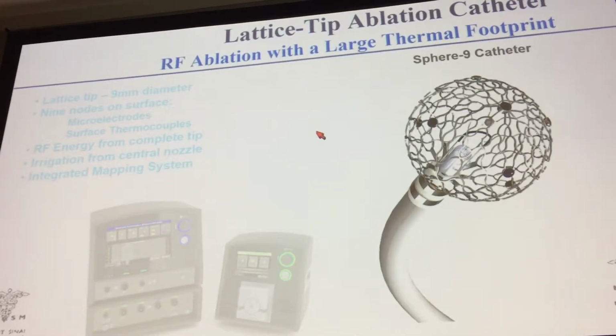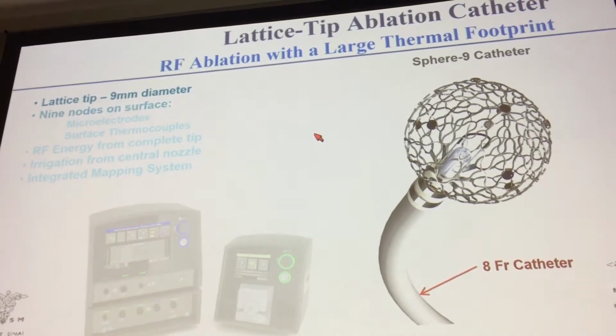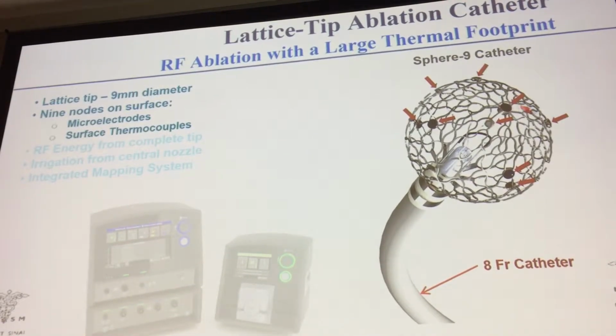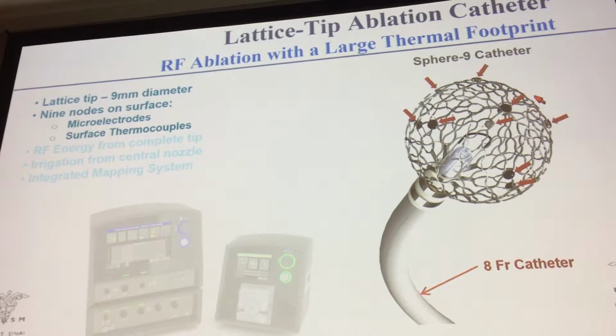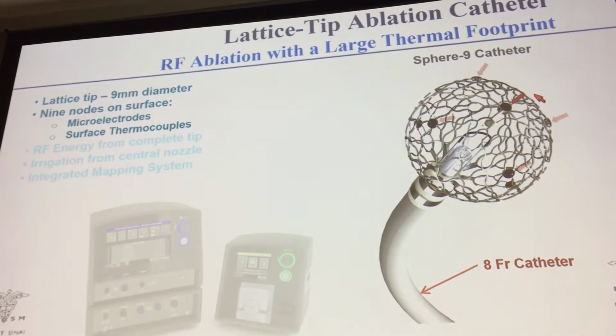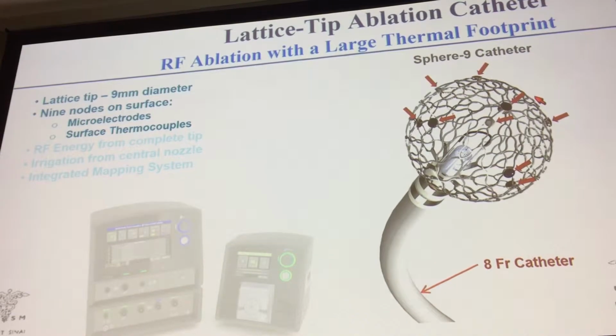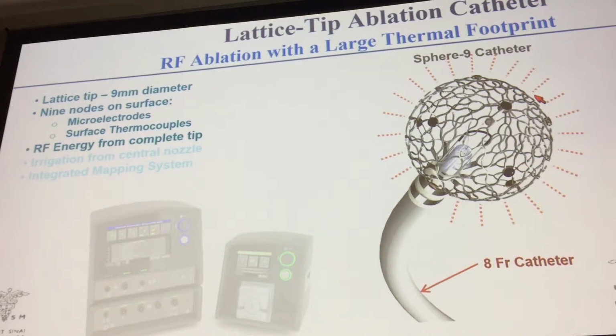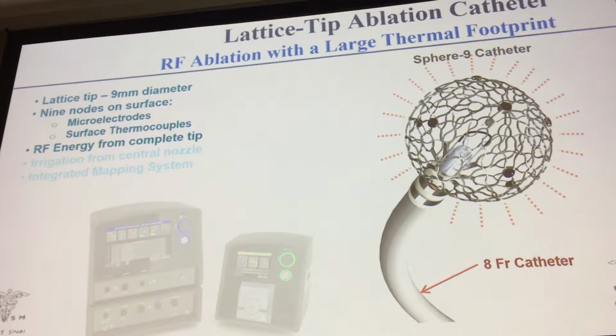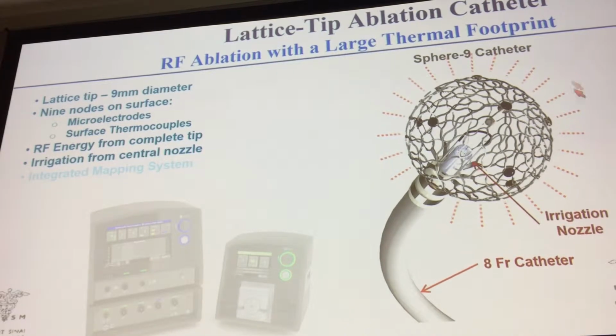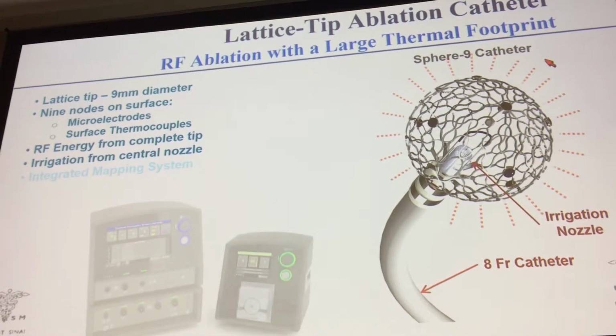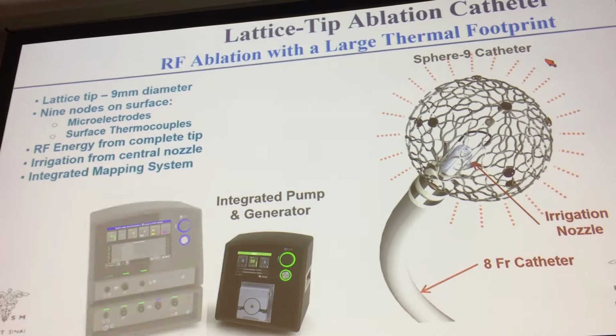This is the system itself. There's the catheter. It's an 8 French catheter with a compressible nitinol tip. It has 9 nodes, each of which contains a microelectrode as well as a thermocouple. What you see is one at the tip, 4 more distal, and 4 more proximal. The whole nitinol mesh delivers energy, and there's irrigation from a central jet. There's an integrated pump and generator as well as the mapping system.